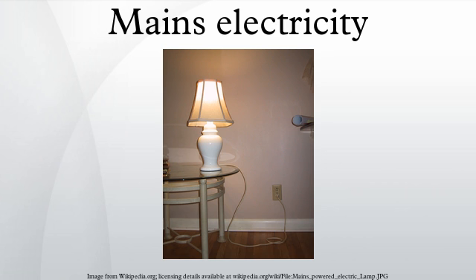A 230 V distribution system will use less conductor material than a 120 V system to deliver a given amount of power, because the current, and consequently the resistive loss, is lower. While large heating appliances can use smaller conductors at 230 V for the same output rating, few household appliances use anything like the full capacity of the outlet to which they are connected. Minimum wire size for handheld or portable equipment is usually restricted by the mechanical strength of the conductors.